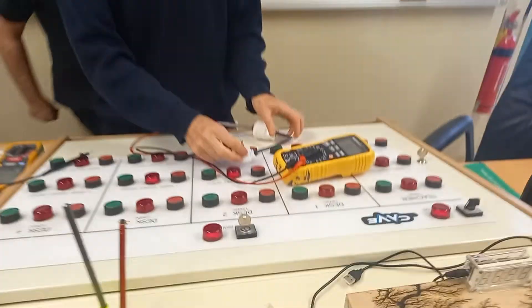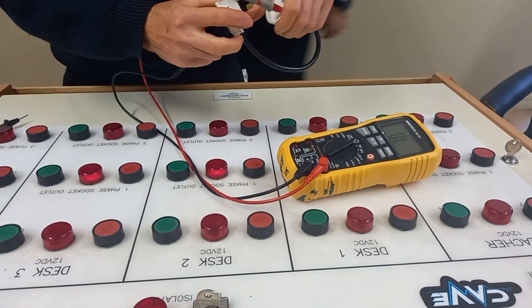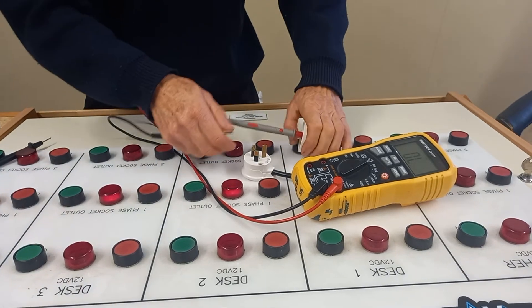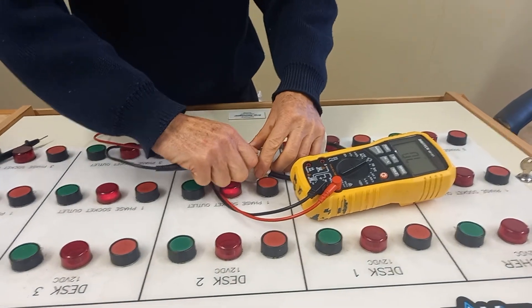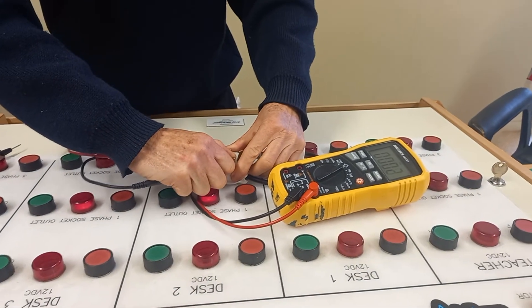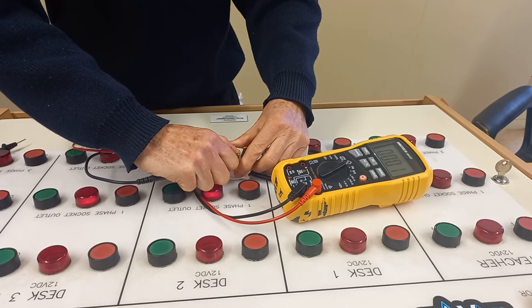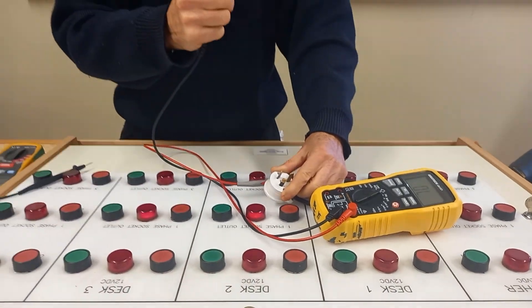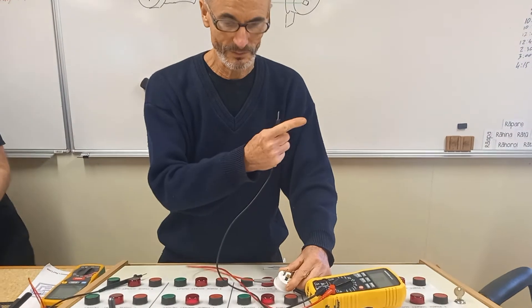The next one, neutral. I'm going there. Expecting low ohms and I'm not disappointed: 0.1 ohms. So it's polarity, it's in the right place. It's continuity, it's continuous the whole way through.